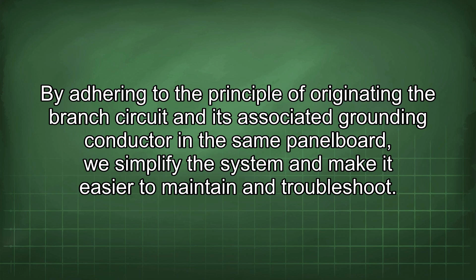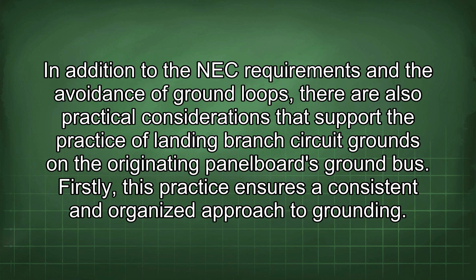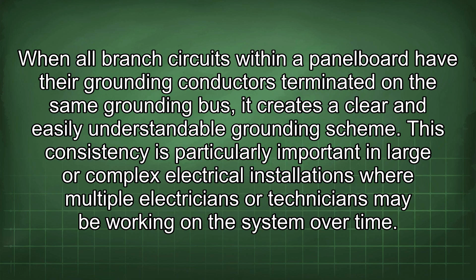In addition to the NEC requirements and the avoidance of ground loops, there are also practical considerations that support the practice of landing branch circuit grounds on the originating panel board's ground bus. Firstly, this practice ensures a consistent and organized approach to grounding. When all branch circuits within a panel board have their grounding conductors terminated on the same grounding bus, it creates a clear and easily understandable grounding scheme. This consistency is particularly important in large or complex electrical installations where multiple electricians or technicians may be working on the system over time.